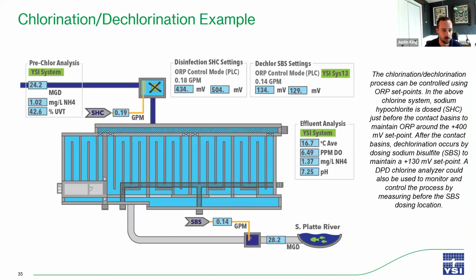All right, and then another way that we disinfect water is with chlorination, dechlorination, which is a typical strategy that is used in wastewater treatment plants and also clean water plants. But for the purposes of this presentation, we'll just talk about chlorination, dechlorination as it relates to wastewater treatment. And so you can use two different types of sensors for this. You can use a chlorine analyzer, which we have as the 3017M chlorine analyzer, where we'll typically place an analyzer at the beginning of the process, sometimes in the middle of the process, and then finally at the end of the process.